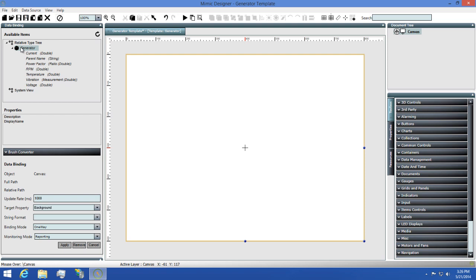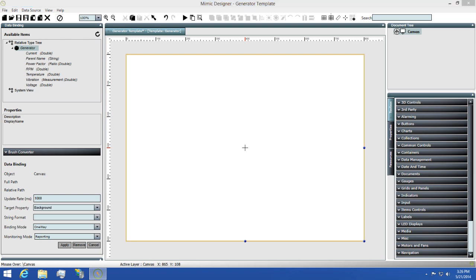It's important to note that when binding to these properties, the bindings are relative which means that they aren't attached to any specific asset. Rather, these bindings are acting as a reference for the Mimic when it's open, pointing the Mimic to the requested assets property paths.